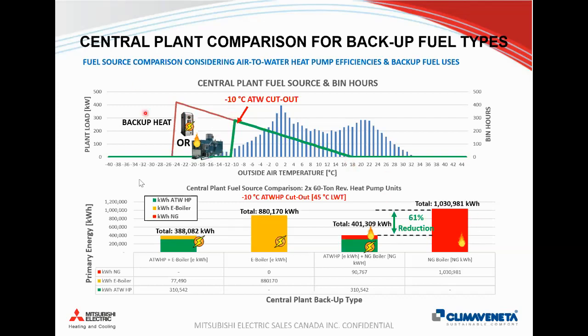If we look at the worst case of all gas in that system, all these bin hours being served by a gas boiler would have approximately 1 million kilowatt hours of energy when you convert cubic meters of natural gas to kilowatt hours. And if we look at an electric boiler, we have a little bit less, about 880,000 kilowatt hours. That's just due to the difference in efficiency, because our electric boiler has a COP of 1 and our gas boiler has a COP of about 0.95.